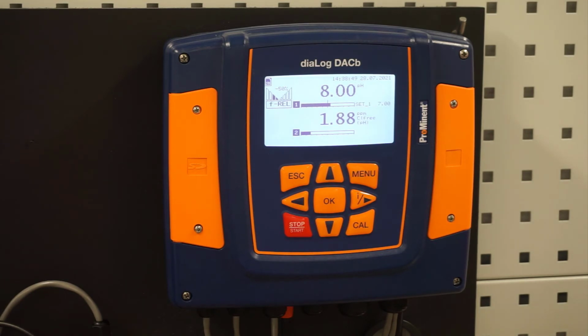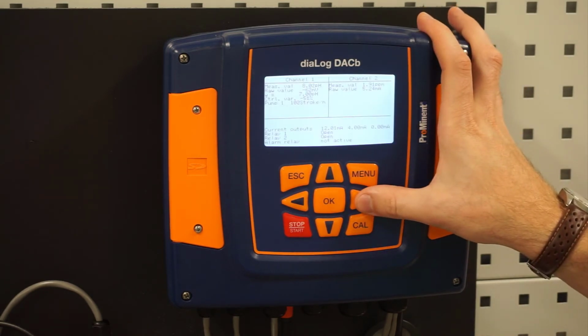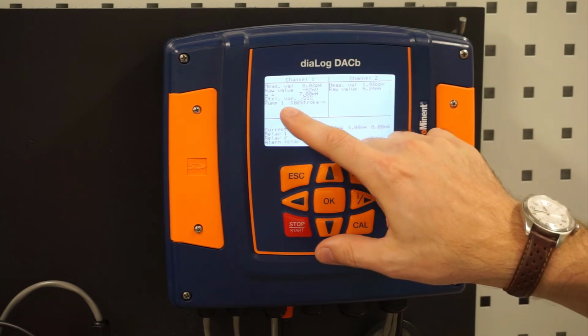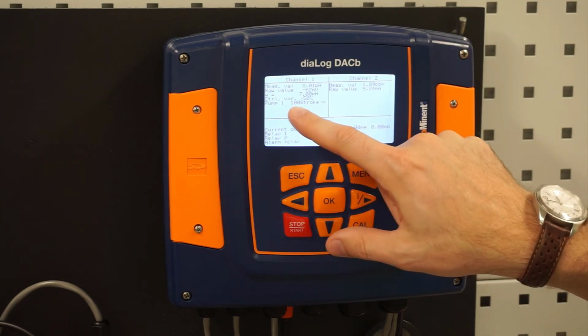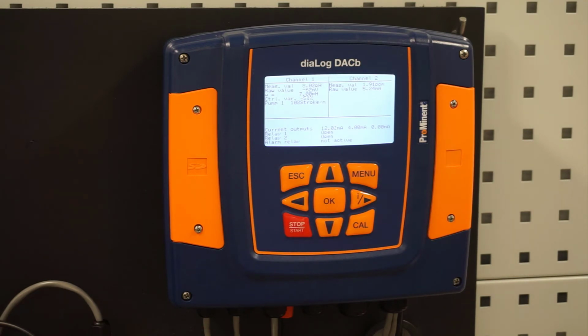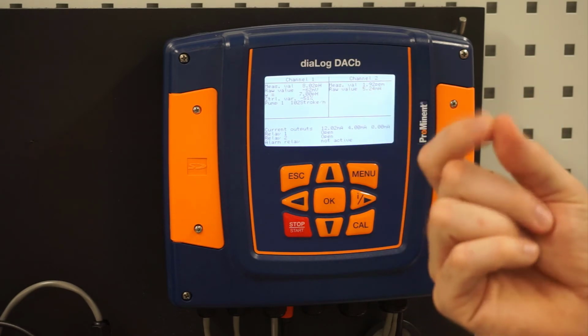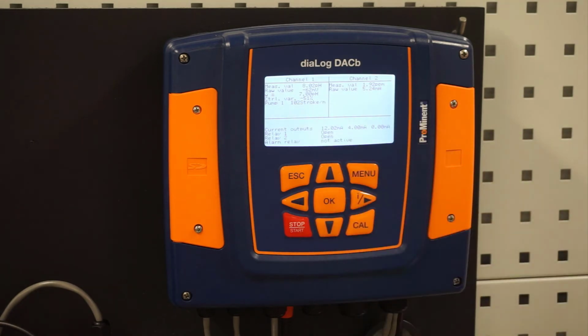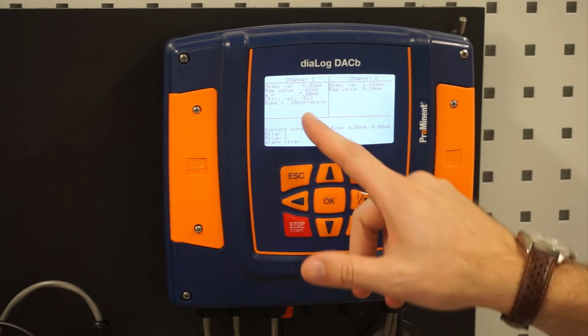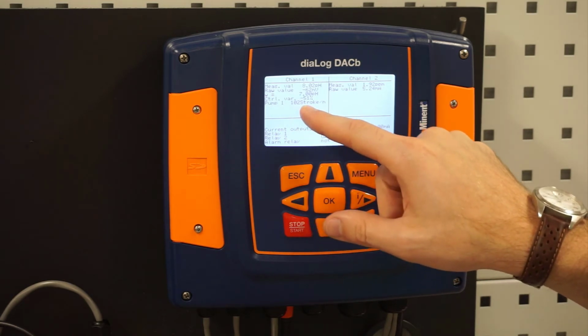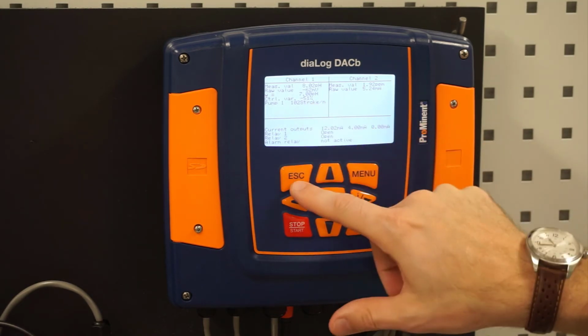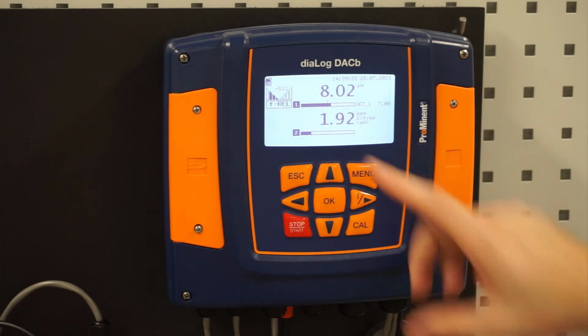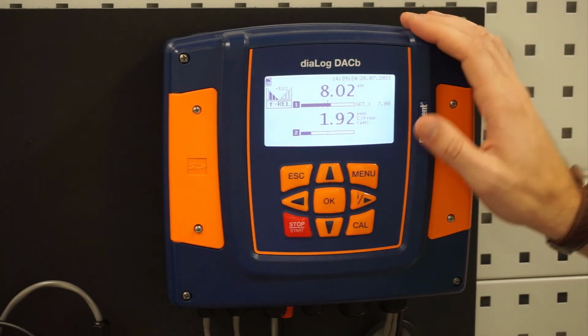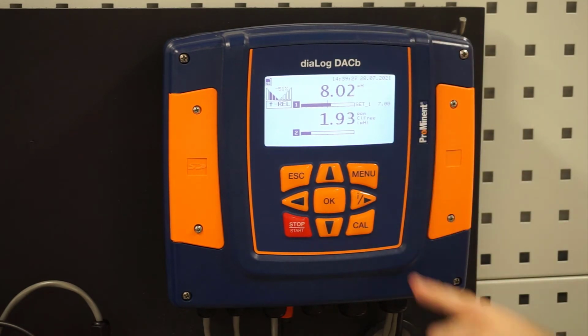Remember, we put 200 strokes per minute. So if I go over to this screen, you can see that my pump is running at half speed, and that's right around 100 strokes per minute. So coming out of that digital output, it's sending a whole bunch of contacts out at a rate of 102 strokes a minute, and that would be speeding the pump up. The closer we got to a set point, that would be slowing down because we'd be getting closer to our set point. We don't want to be at full speed here, or else we'll blast past the actual set point.